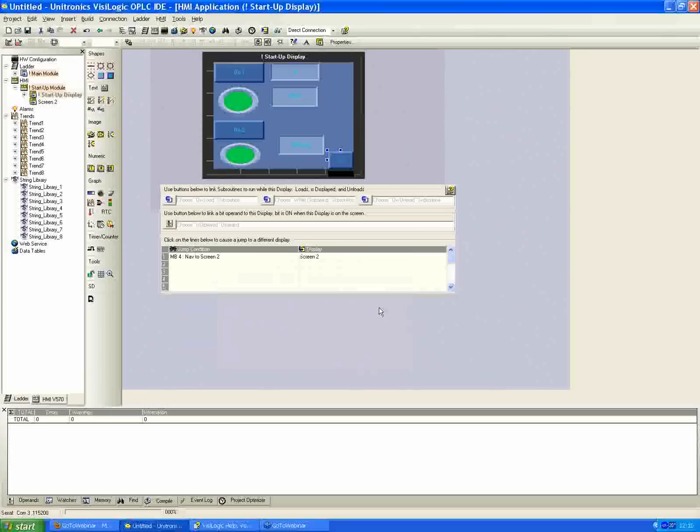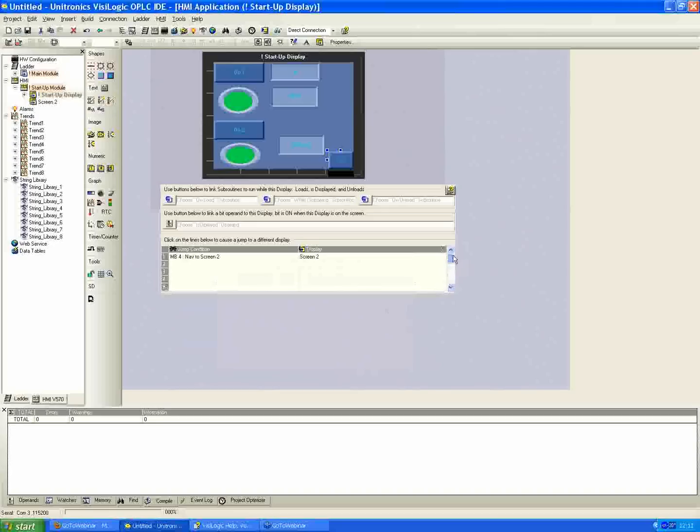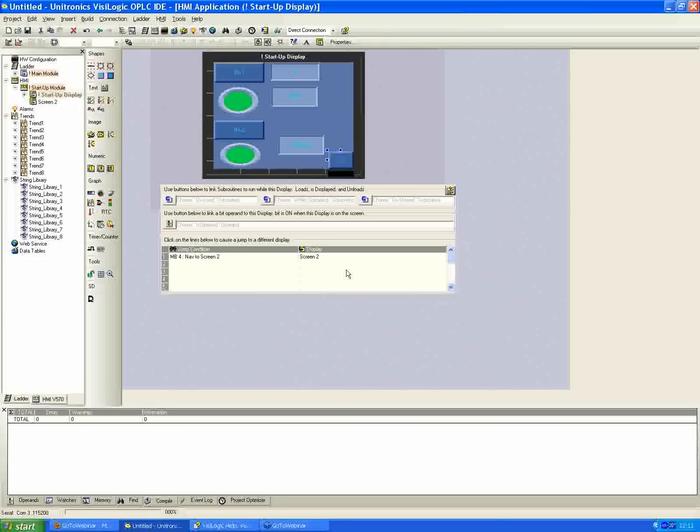That's really all that you have to do to be able to jump between screens. You can see there's a bunch of different, you have up to 16 different jump conditions you can do. So you can jump to 16 different screens via the HMI here. If for some reason you do need more, you can always implement it with ladder code as well.